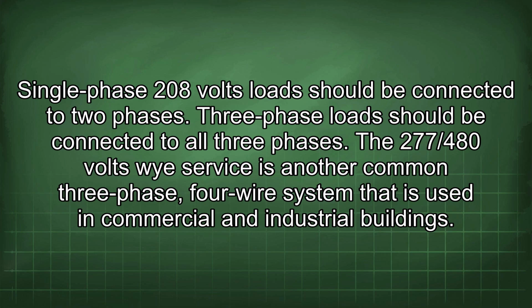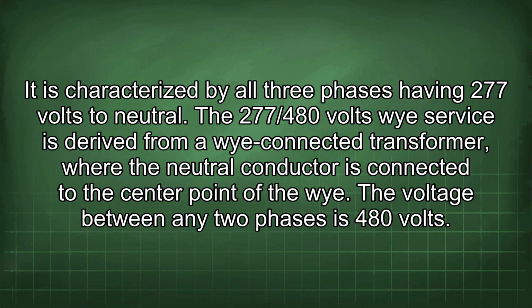Three-phase loads should be connected to all three phases. The 277/480 volts Y service is another common three-phase, four-wire system that is used in commercial and industrial buildings. It is characterized by all three phases having 277 volts to neutral.